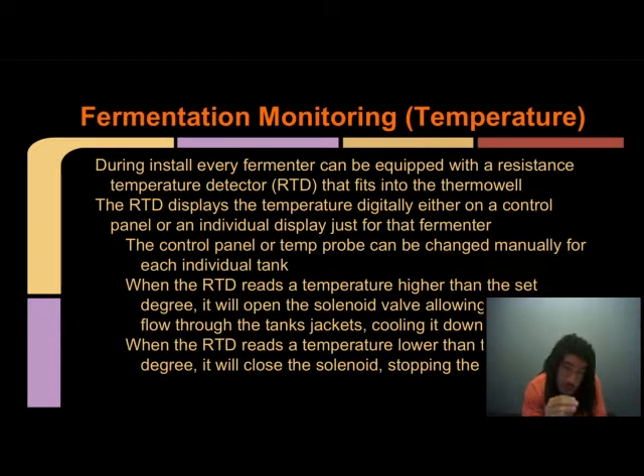When the RTD reads a temperature higher than the set degree, it will open a solenoid valve, allowing the glycol to flow through the tank jackets, cooling it down. When the RTD reads a temperature lower than the set degree, it closes the solenoid valve, stopping the glycol flow, keeping it from cooling down too far, allowing it to free rise back to where it's supposed to be, or to stay where it's supposed to be.